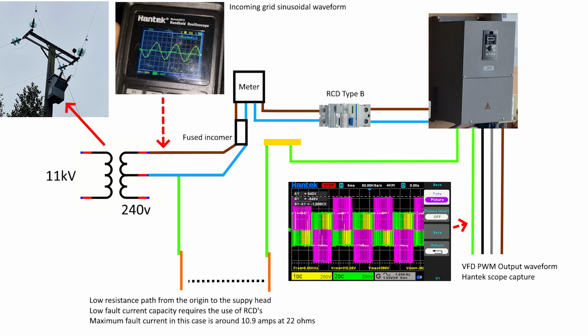A certified electrical contractor can come and test your earthing setup and see if it conforms with the standards. I installed a new earthing rod array for the building and it was certified within 22 ohms. Anything below 100 ohms is permitted for a TT install, but with a TT or any system that uses an earth rod as the main earth reference, you will not be able to carry the full fault current back to the transformer's star point. You ideally need an RCD protection with a TT system for safety, and I would recommend strongly RCD protection regardless of your electrical system.